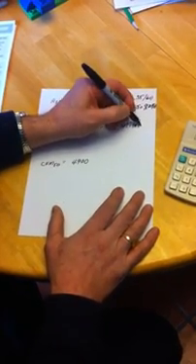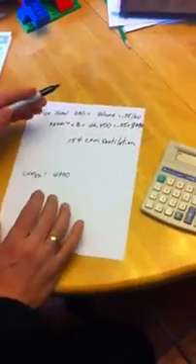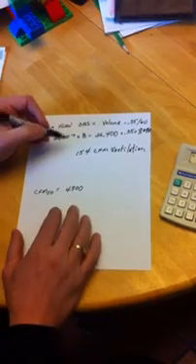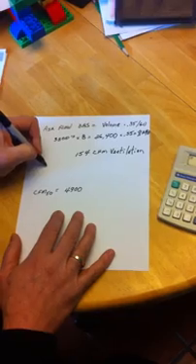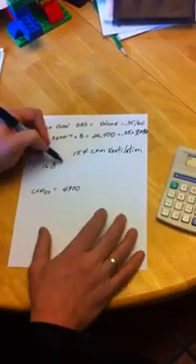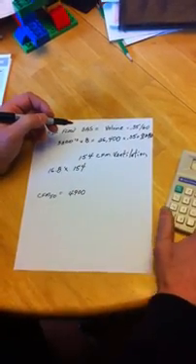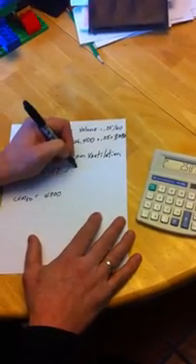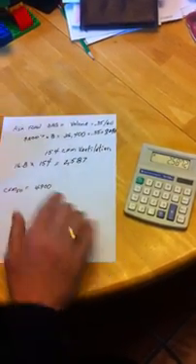Now we're going to figure out what that would be in a blower door number. There's a number called an N factor, and that's the factor we multiply this by to figure out what the blower door number would be at minus 50 pascals. The N factor for this area in a story-and-a-half building like this is 16.8. So we multiply 16.8 times 154, and that gives us 2,587 CFM.